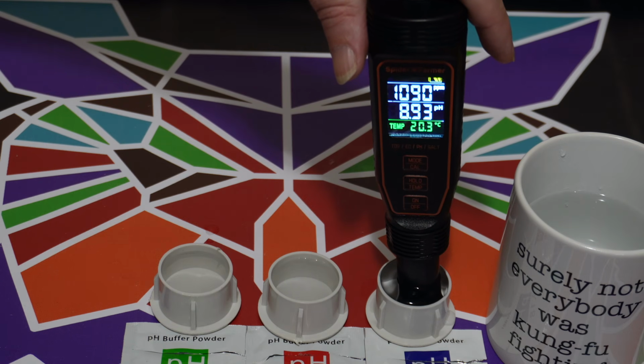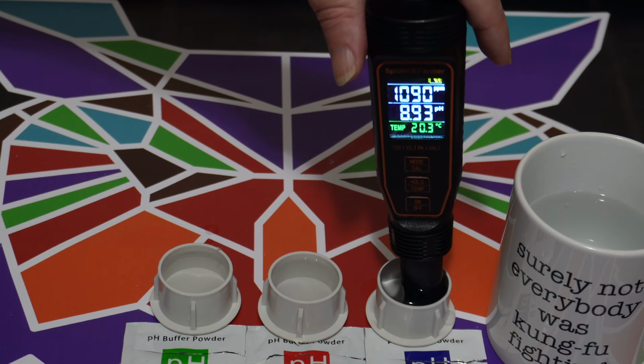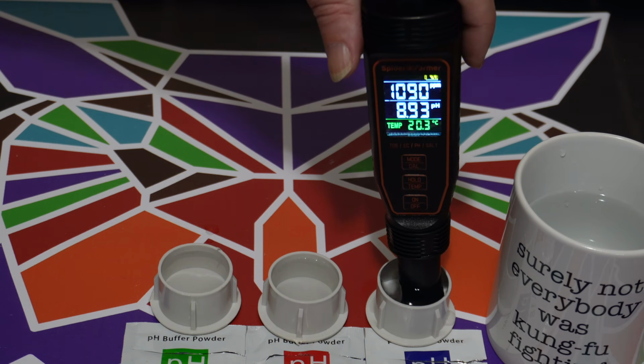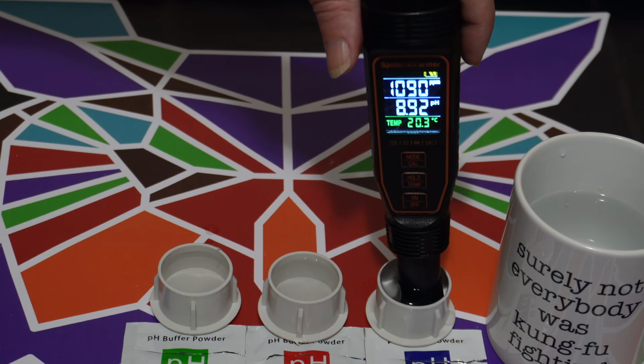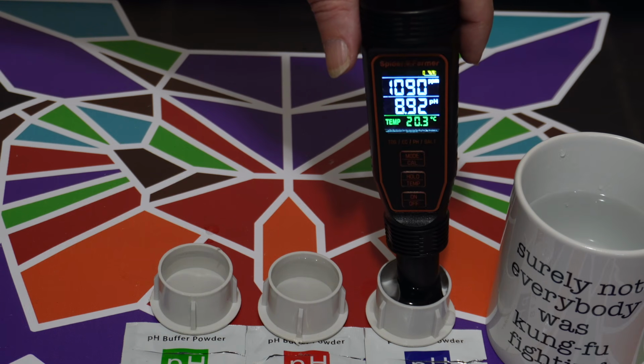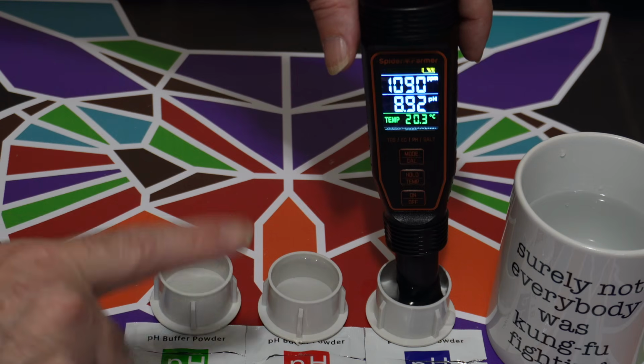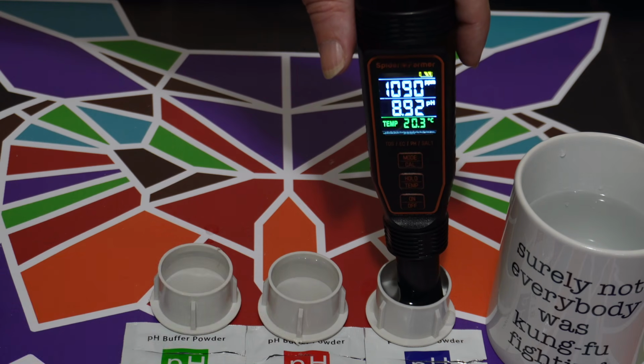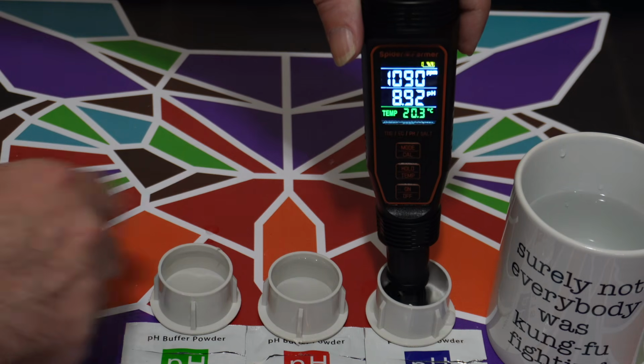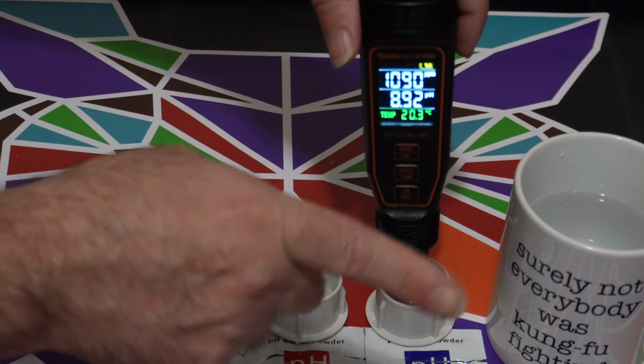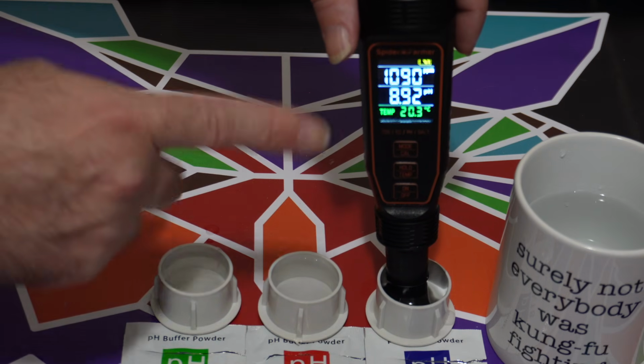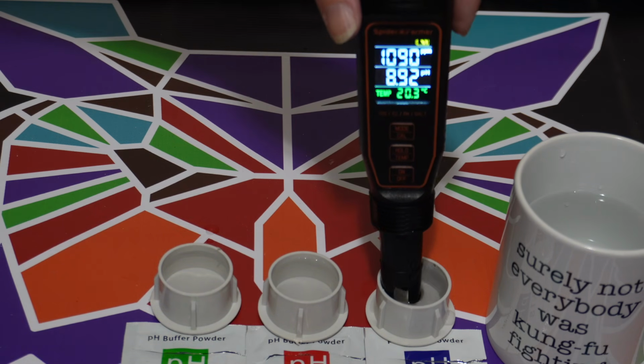So as you guys can see, there is a bit of variability, 8.93 is pretty much what it's sitting at instead of the 9.18. There is a little bit of variability, guys. This is not an accurate pinpoint tool. It's within the realm of reason. It's not going to screw you up too bad. Well, it's not going to screw you up if you keep this thing calibrated. So make sure you hold on to that other solution. You're checking these things weekly, because if this was reading 7.2 or, you know, 10.3, you'd have a really big problem and it would no longer be accurate. So that is how we are looking here.